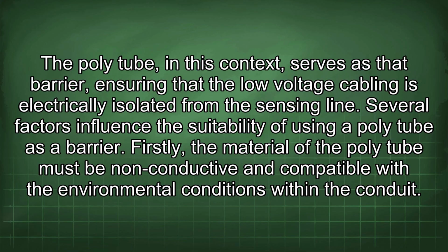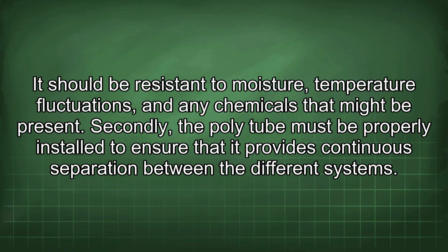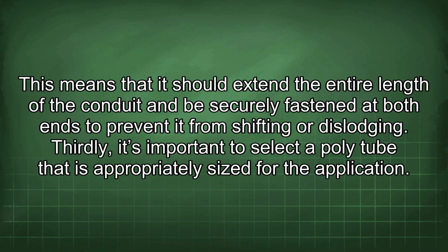Firstly, the material of the polytube must be non-conductive and compatible with the environmental conditions within the conduit. It should be resistant to moisture, temperature fluctuations, and any chemicals that might be present. Secondly, the polytube must be properly installed to ensure that it provides continuous separation between the different systems. This means that it should extend the entire length of the conduit and be securely fastened at both ends to prevent it from shifting or dislodging.